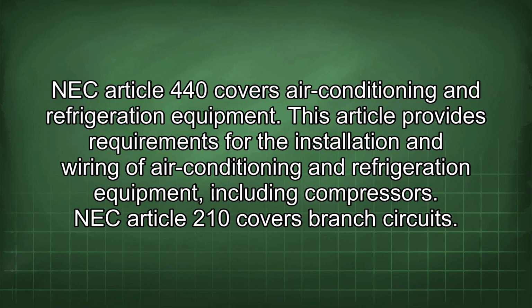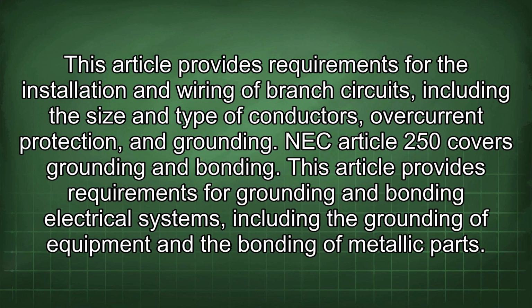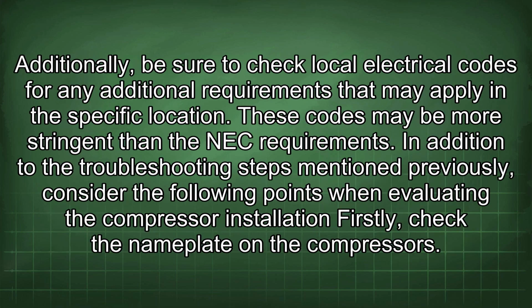NEC Article 210 covers branch circuits. This article provides requirements for the installation and wiring of branch circuits, including the size and type of conductors, overcurrent protection, and grounding. NEC Article 250 covers grounding and bonding. This article provides requirements for grounding and bonding electrical systems, including the grounding of equipment and the bonding of metallic parts. Additionally, be sure to check local electrical codes for any additional requirements that may apply in the specific location. These codes may be more stringent than the NEC requirements.